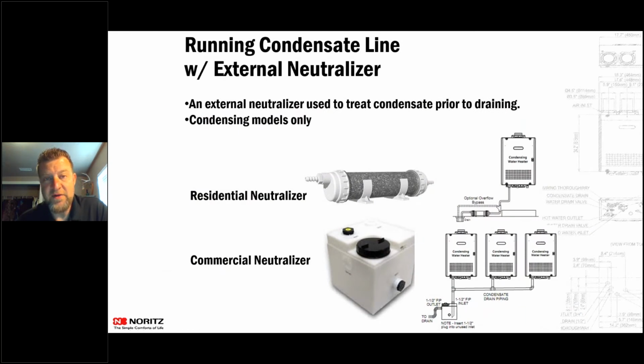There are areas where they will want you to neutralize that condensate coming out. There are residential neutralizers and commercial neutralizers. For a unit like this, you would bring that condensate down into the bottom here. It would actually fill this up and come up out of the top of that. But what we don't want is for it to come down and create another trap inside of there. If you are running it down and creating another trap inside of there, you'll want to put a Y into that condensate line to allow air to get in there to be able to push that through that trap. So you're basically just adding a vent into that condensate drain.